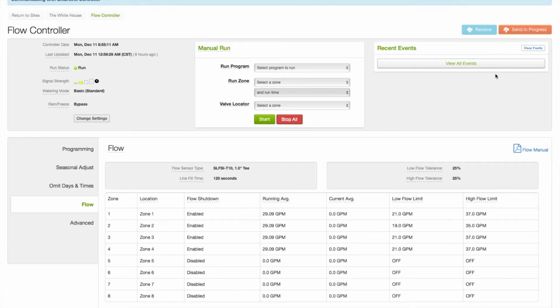So if you have a high flow or a low flow alert and the controller has not been running, and you say, well, how did I get this alert when the controller didn't even run? That's why. It has to have a good run, a good flow event, before that error will clear.